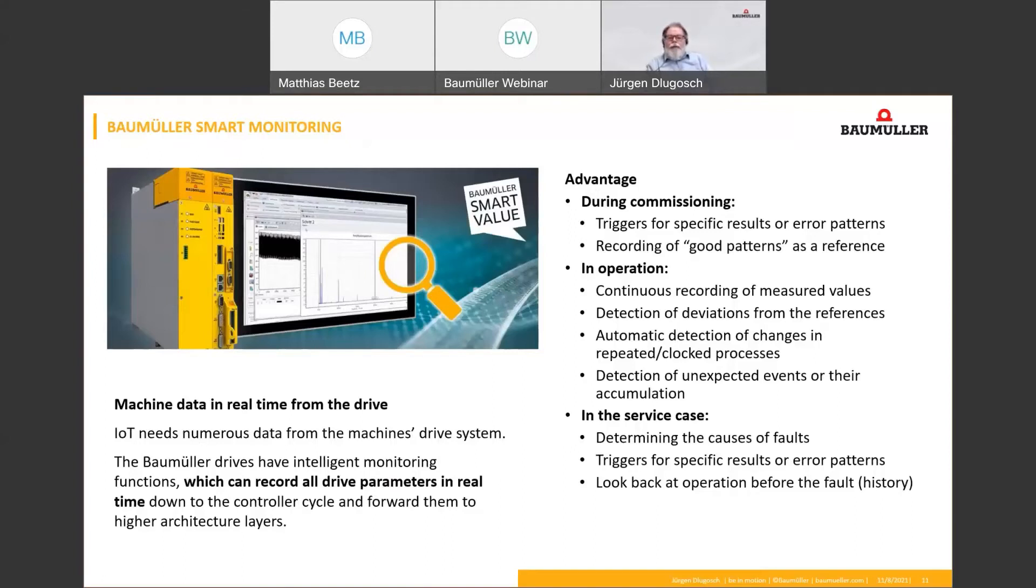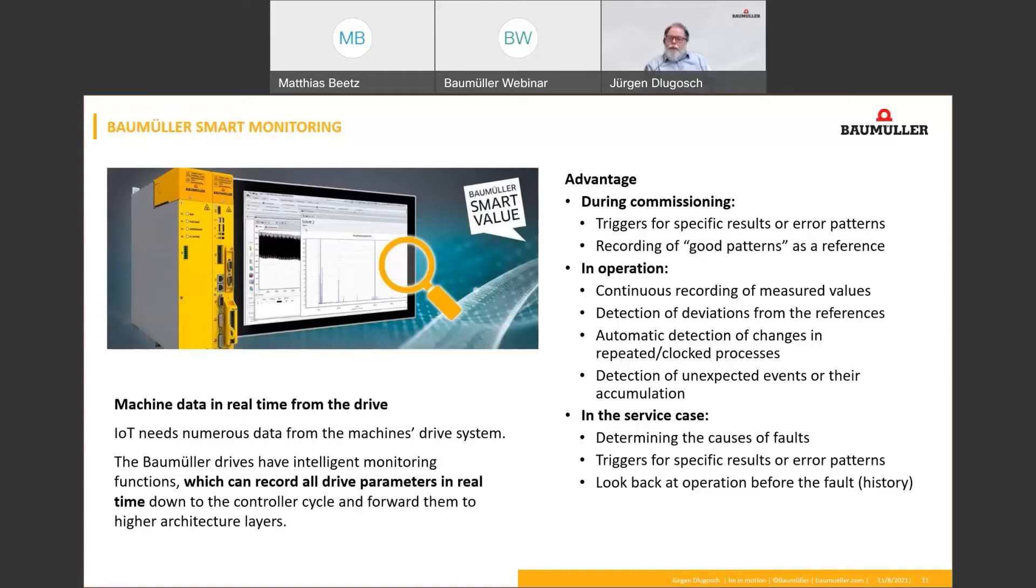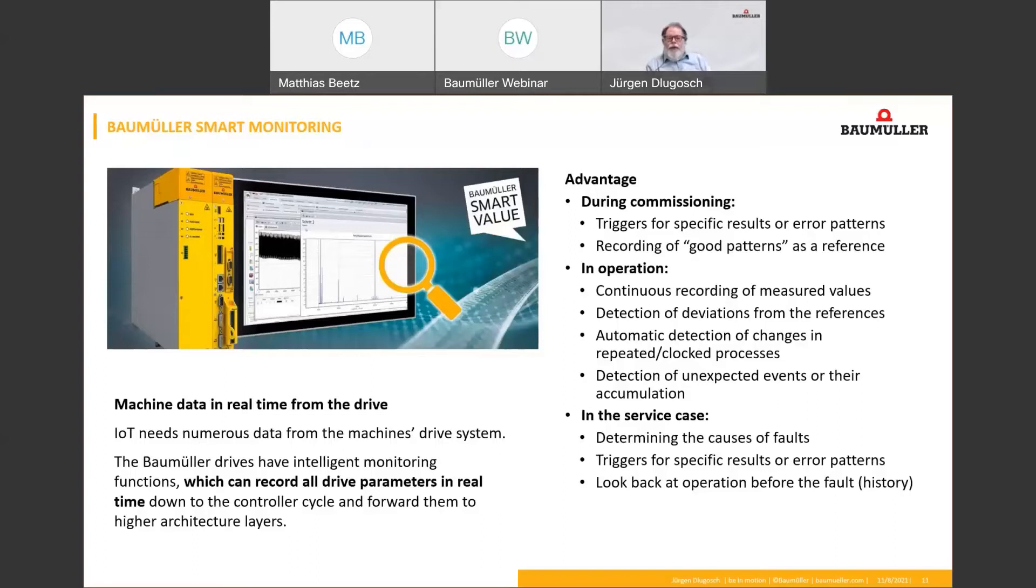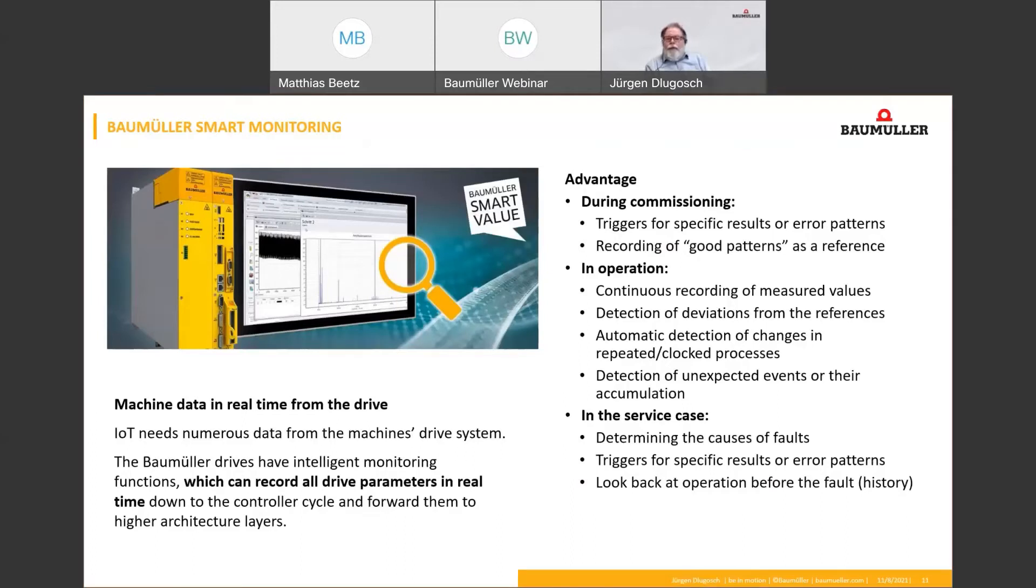Here are a few use cases for Smart Monitoring. During commissioning, a reference can be recorded. This reference could be compared with the actual situation of the machine to detect some differences between commissioning and actual situation. During operation, it's possible to make an online data sampling to detect intermittent events that you can see that something changed on your production or on your process immediately. And also, what is very important in service cases, the monitoring function could be triggered on events maybe caused by errors and you can check the data history for analysis on it.